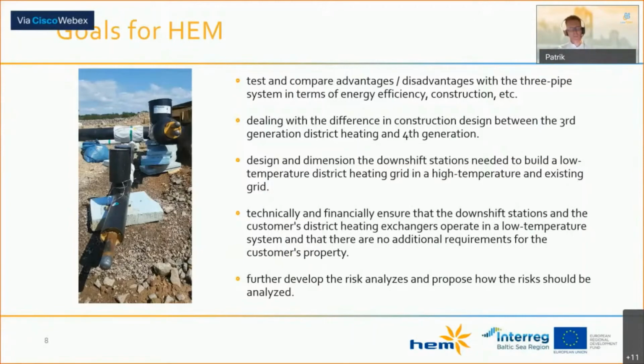handling the construction, so we are actually able to put a low-temperature district heating grid within a high-temperature district heating grid, and being able to choose whether it is good or bad. We are monitoring, we are seeing if it's working, and if it's not, we can choose to change it back. But we are certain that it will show us what we are expecting to see: less energy losses and better economy for the customers. It's important to make it work in general.